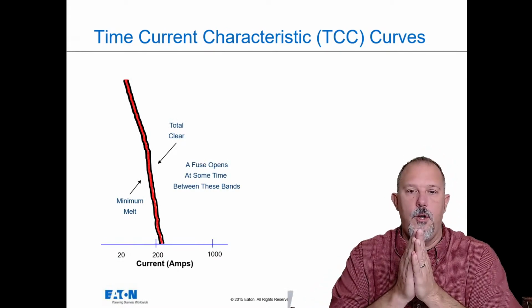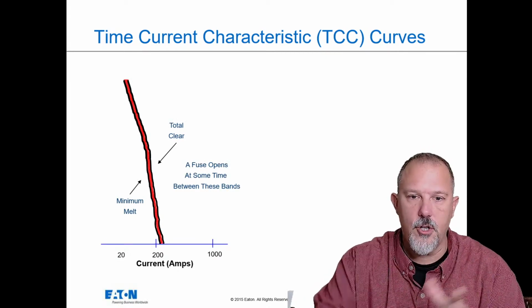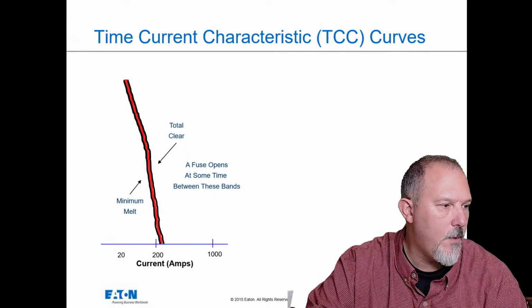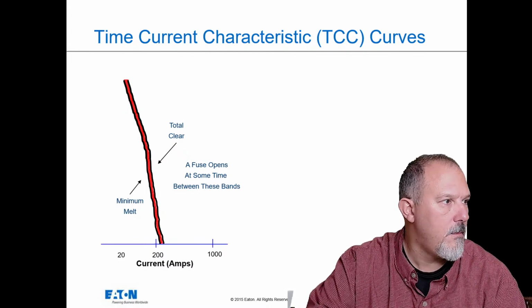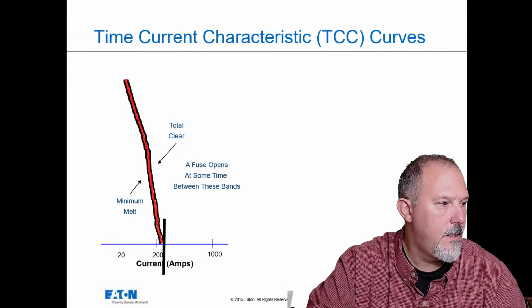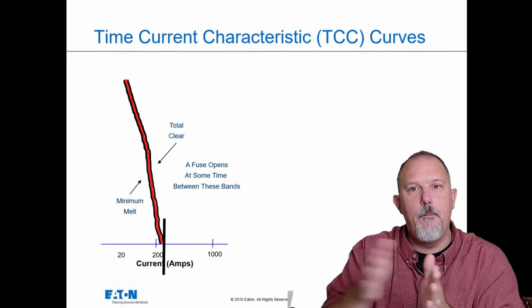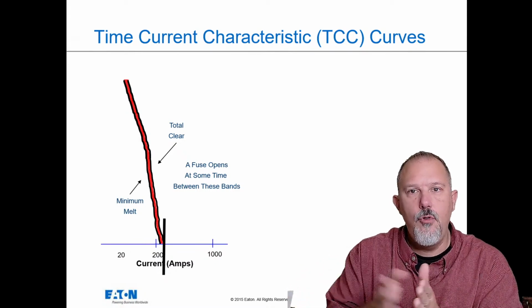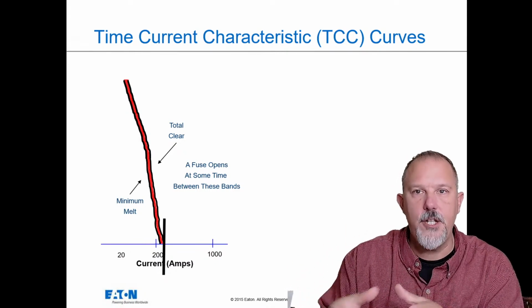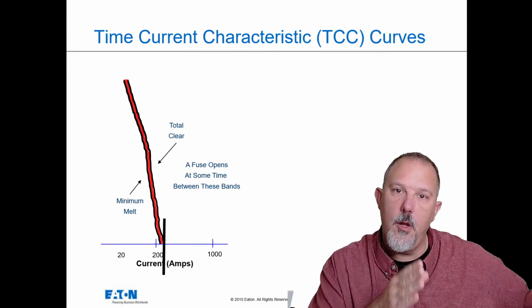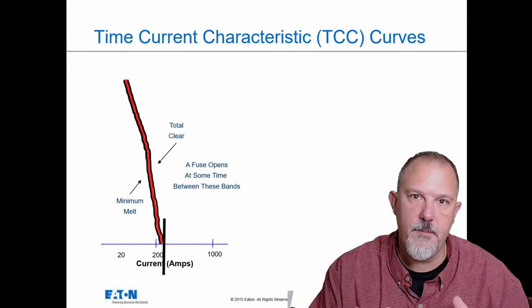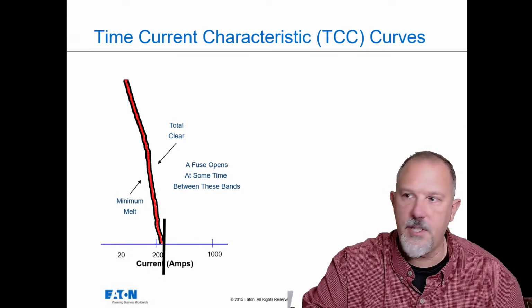Now, at what point does a fuse go into the current limiting region? It is where we cross 0.01 seconds. So if I wanted to draw a line at that point, I would draw it right here, and I'm going to make it nice and fat. Currents above that point move you into the current limiting region of a fuse. Currents below that point are not in the current limiting region.